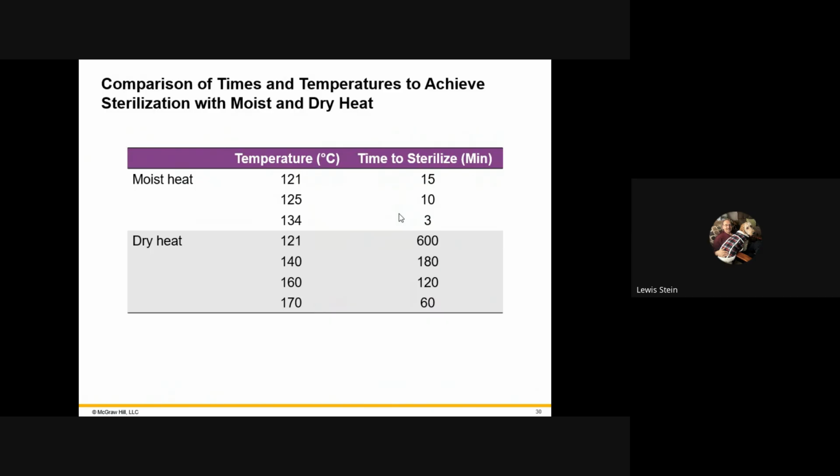You use, basically, a pressure cooker. The name that you will see and we will describe is the autoclave, 121 degrees Celsius, which is about 252 degrees Fahrenheit. We do it in Celsius. At 15, in a closed system, since temperature, pressure, and volume all have a relationship, it will reach in that closed system, like a pressure cooker, 15 pounds per square inch. So if you look at just the meter and it's only in PSI, you know it's 121. So the PSI is a critical piece.